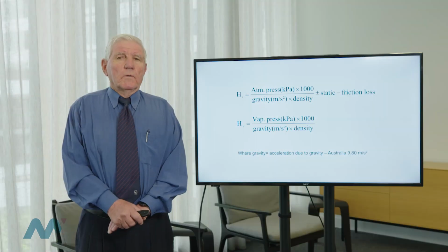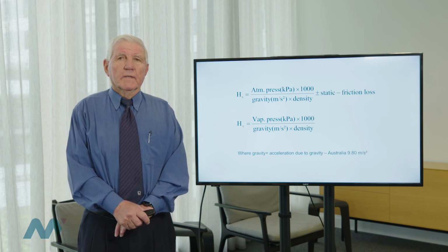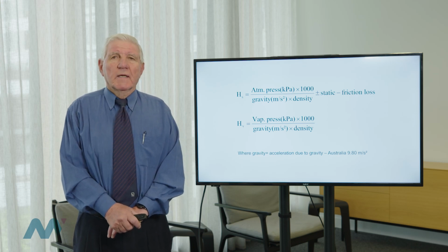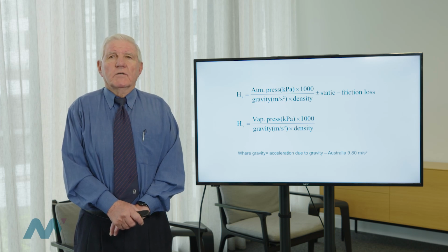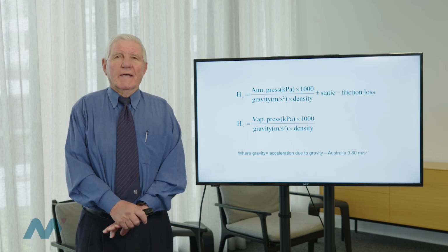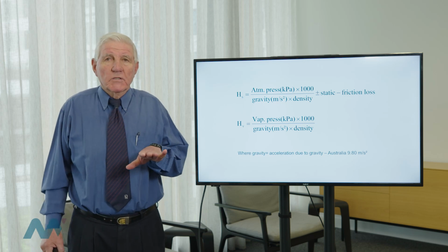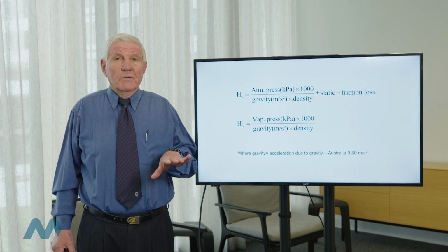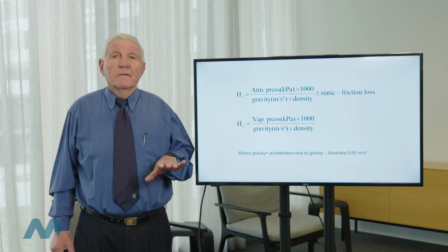When it comes to pressure at the pump, the point that's important is what's happening at the suction flange. Okay? And if you've got a gauge somewhere close to the suction flange, whether it's positive or negative may not be an issue. It's a question of how negative it might be. Because remember that when we're talking about NPSH, we're not talking about from atmospheric pressure, we're talking about from absolute zero. So we've got something like 100 kPa to play with.